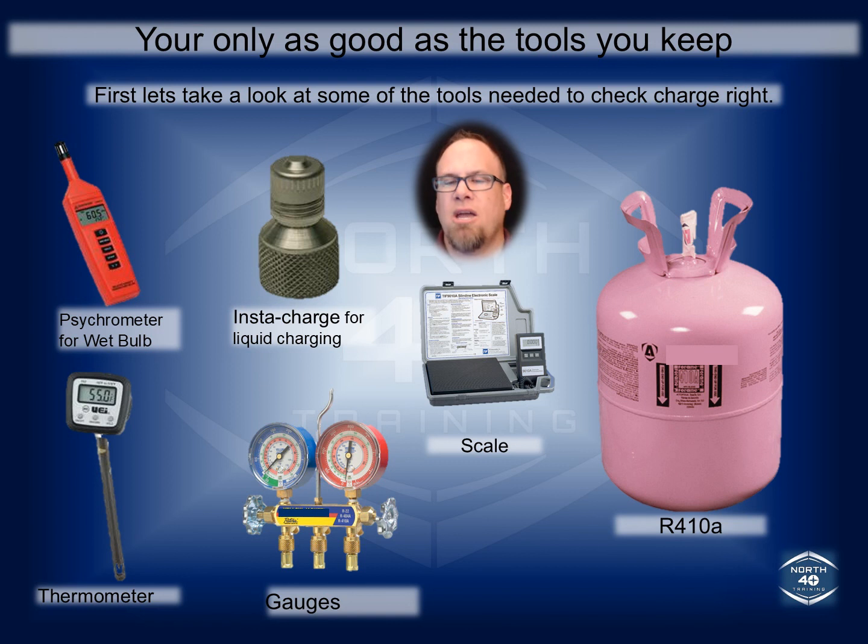And then, of course, pay attention to the refrigerant that you're using. If you notice on this refrigerant bottle, we've got arrows, and here they're pointing towards the bottom end. What that's telling me is that you charge with this end up. So in reality, if I wanted to use this tank right here to charge a system, I'd have to turn it upside down, and the purpose is to pull out in liquid form.